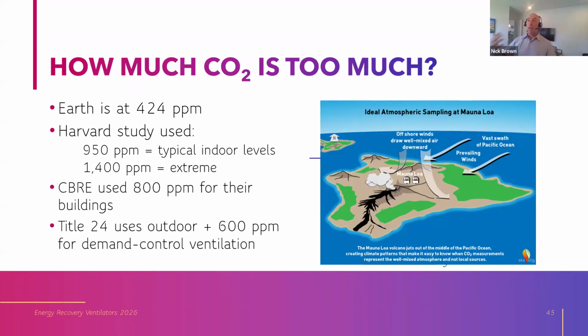But CBRE, a major owner of commercial real estate, used 800 in a presentation I sat in as their target. And for another data point, Title 24 uses outdoor concentration plus 600 as the trigger for demand control ventilation to kick in, which would be maybe 1,050. So it's up to you. There's no real standard-making body who's determined the right amount of CO2.